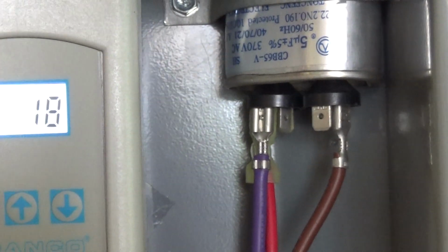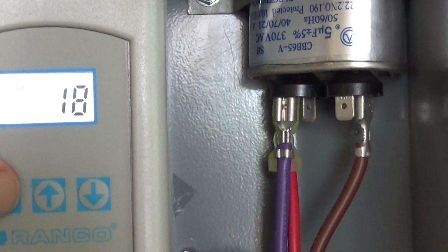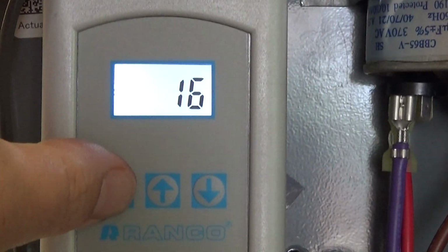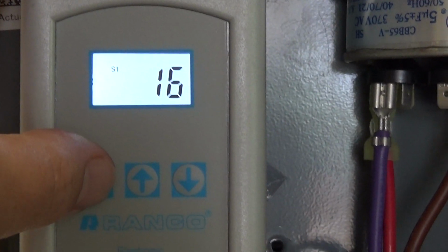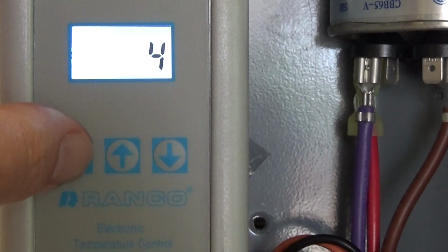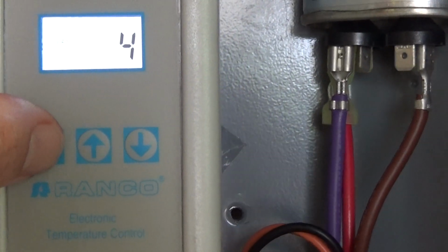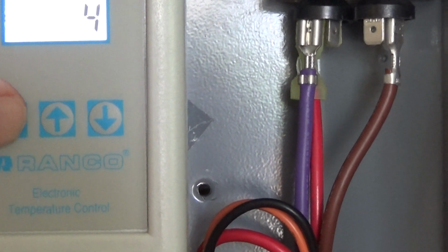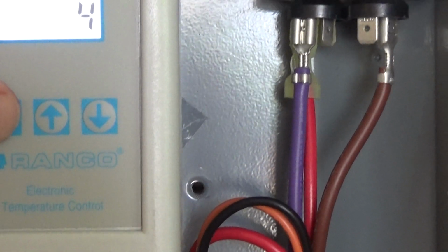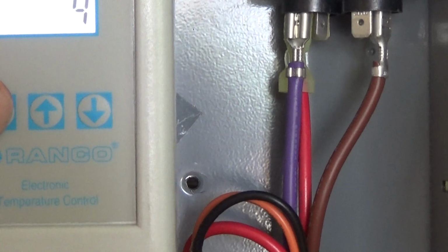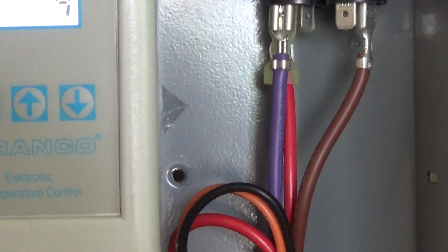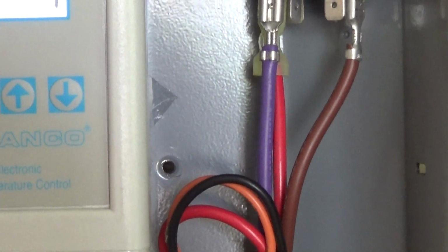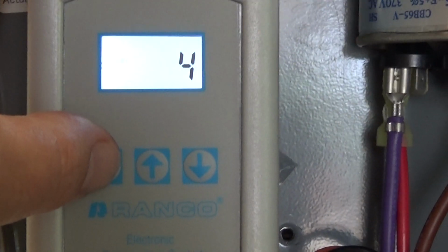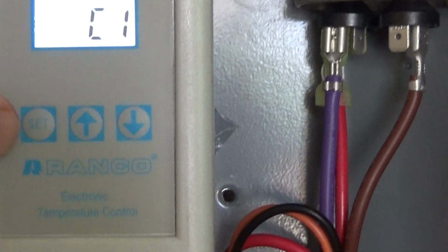Our chiller, which is running right now, we have set at a set point of, I'm sorry, it's set at 16 degrees Celsius with a differential of 4 degrees. So when we get up to 20, the chiller will start cooling again. So what does that mean? That means you're going to have incoming chilled water fluid between 16 and 20 degrees. Preferably you want a bigger differential coming into the glycol side of that heat exchanger.